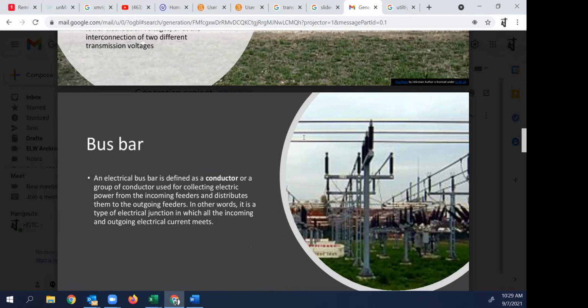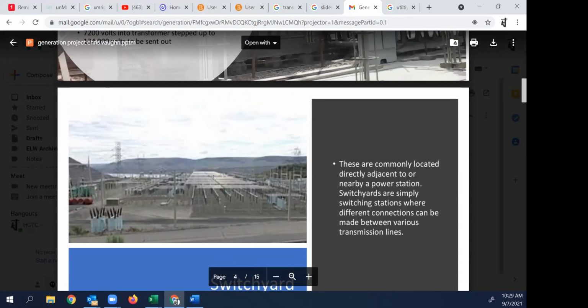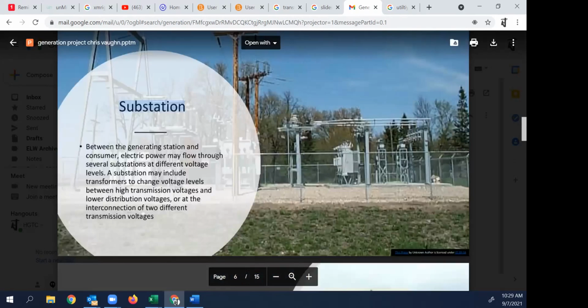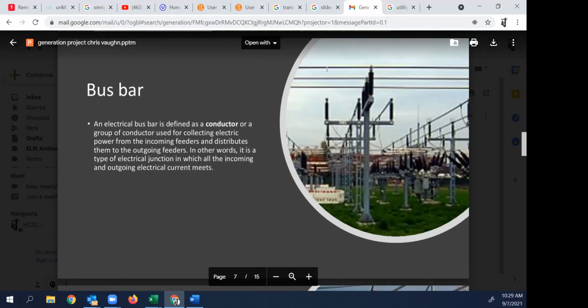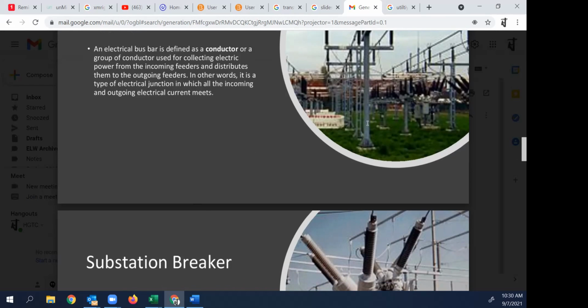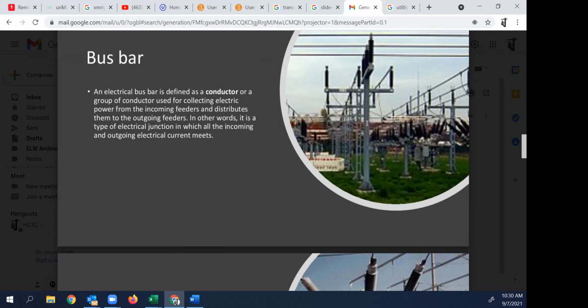The benefit of using bus bar, in both instances in substations or a switch yard, is that it can carry very high current. It's a solid piece of metal, not a conductor like wire. It's more expensive, but we're able to put high current on these and use them to distribute high current. We can't do that on power lines, obviously, so we have to use something like aluminum wire instead.